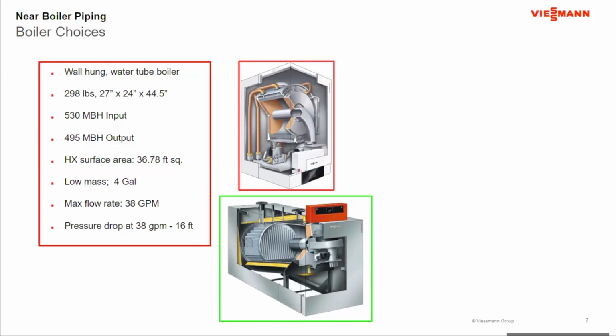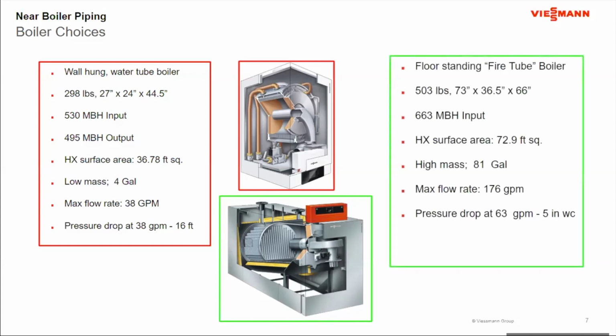Now, the other boiler is a floor standing boiler. Okay, so this floor standing boiler is of a fire tube design. It's a very unique fire tube, but when it really gets boiled down, it's a fire tube boiler. Okay, compact is not part of the design criteria. This boiler weighs 503 pounds, and its footprint is 73 inches by 36.5 inches, and it's 66 inches tall. It's 663,000 BTUs. Why I chose that size is, if I look at the wall-hung boiler, that's the largest of the wall-hungs. This is the smallest of the floor standing in that commercial line. So they're sequential in the size of the boiler. That's why I chose them for this discussion, okay?